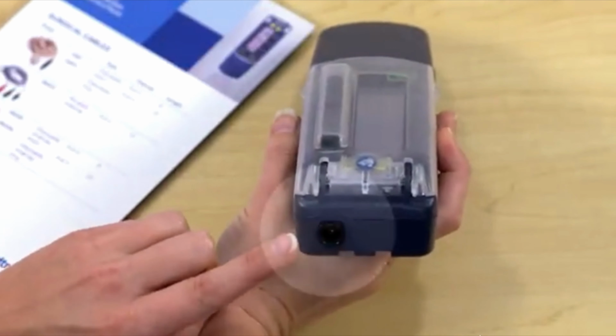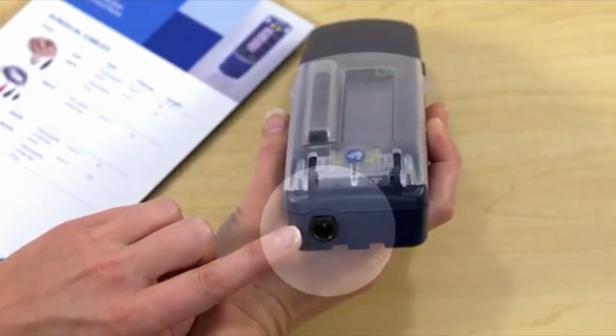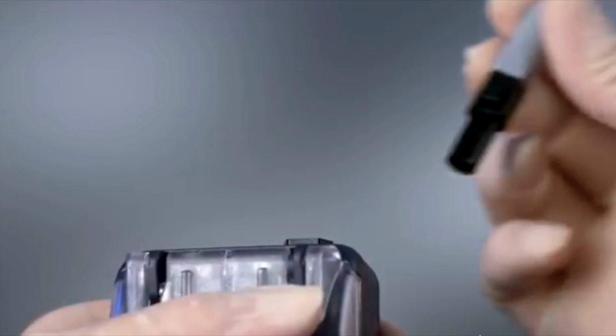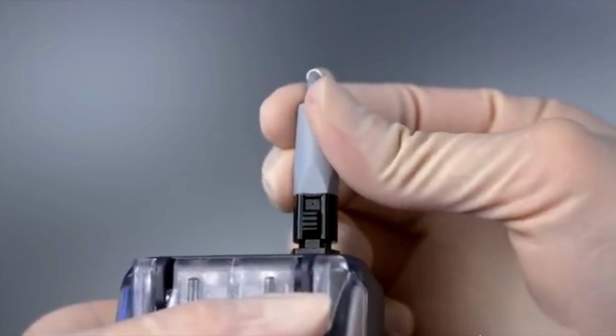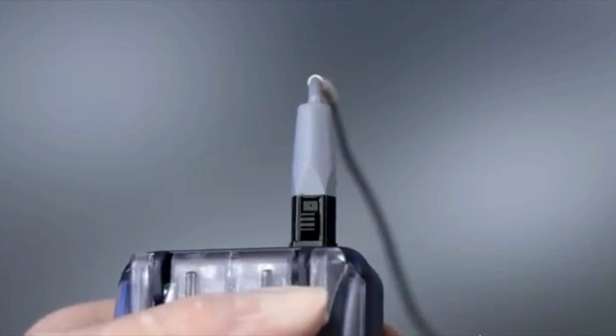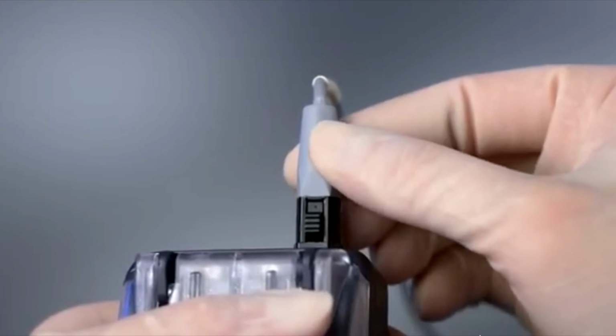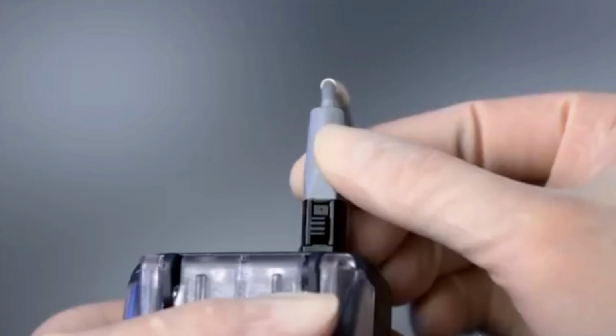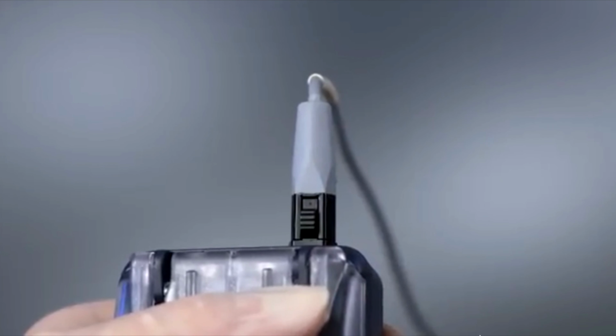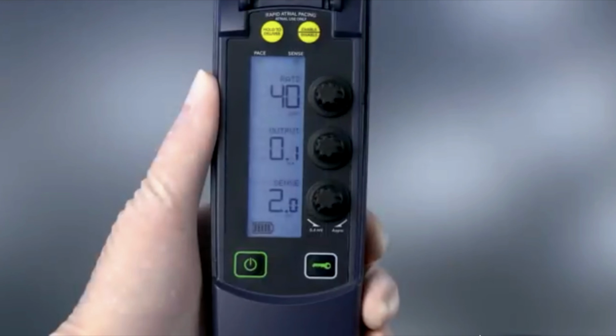Plug the pacing cable into the socket located on the connector block on top of the temporary pacemaker. Verify that the cable end clicks when it is inserted into the temporary pacemaker connection. The audible click signifies that the plug is completely inserted into the receptacle. Note the sense indicator is flashing, which means the device is detecting the R wave.